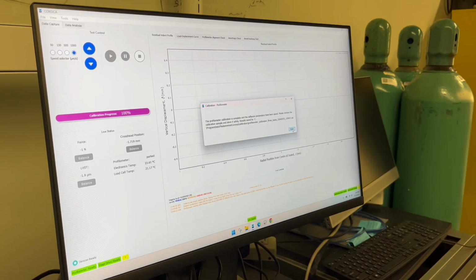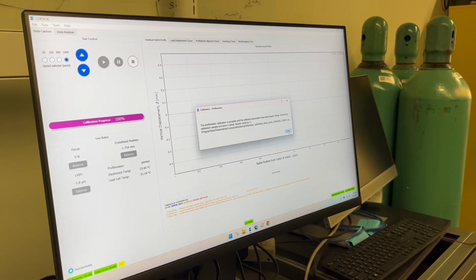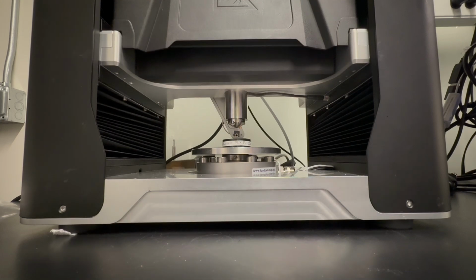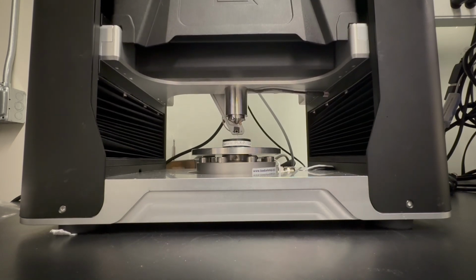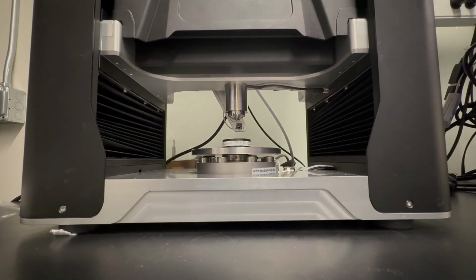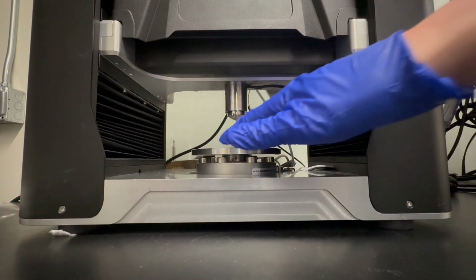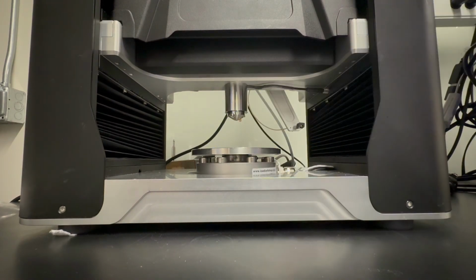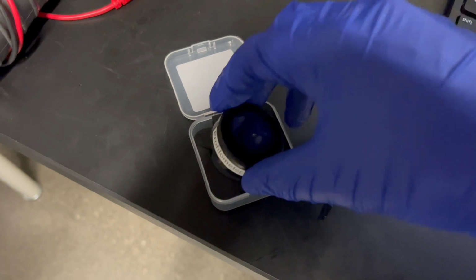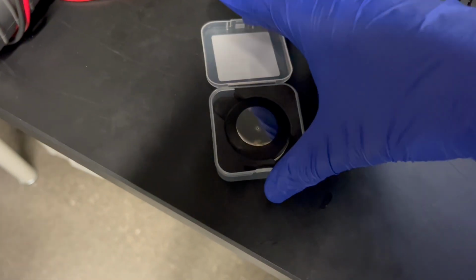Once the calibration is complete, this screen will appear and you can go ahead and select Finish. And then once that's all done, you're ready to remove the calibration sample and then go ahead and place in the sample that you're trying to test. It's very important when placing or removing a sample to be extremely careful not to touch the profilometer. Now you can go ahead and put the calibration sample back in its container and go ahead and put it away.